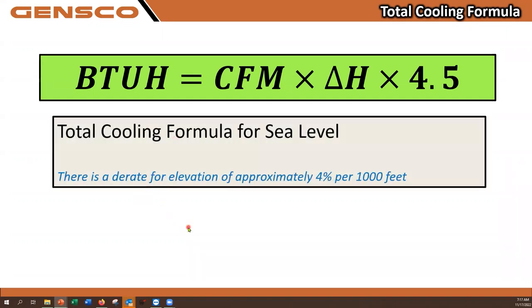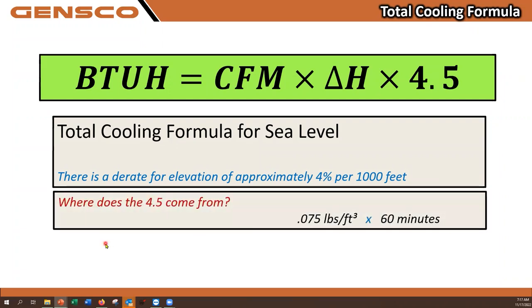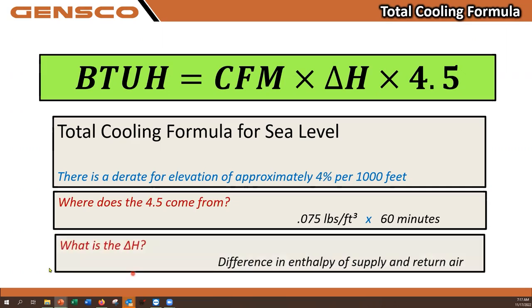So again, this is for sea level. The 4.5 is a constant. That comes from .075 pounds per cubic foot of air, average for 77-degree air at sea level, and 60 minutes, because again, we're dealing with BTUs per hour. And CFM is dealing with cubic feet per minute. So what is the delta H? Again, that's the difference in enthalpy, amount of BTUs that are actually in the air per pound of air.